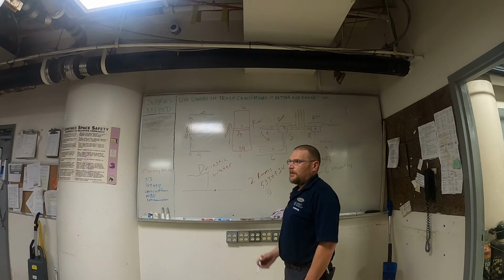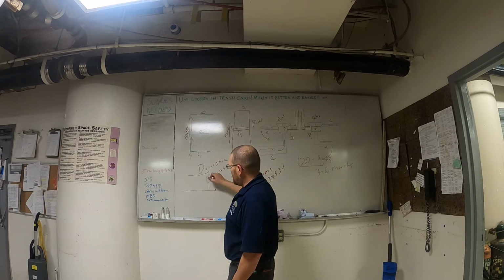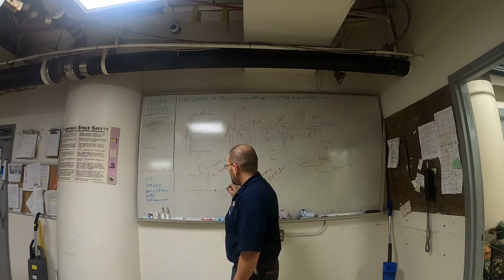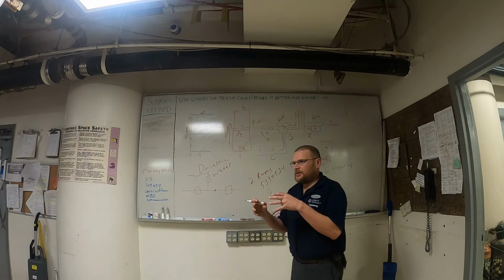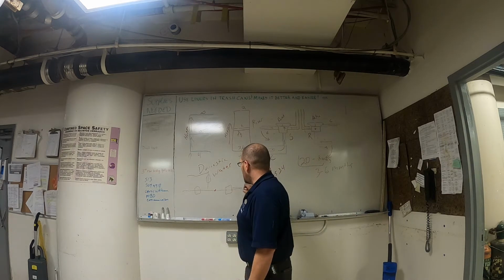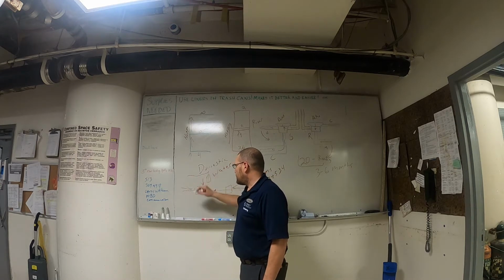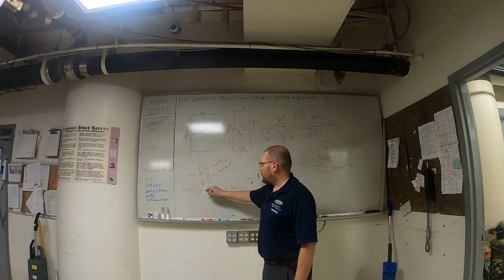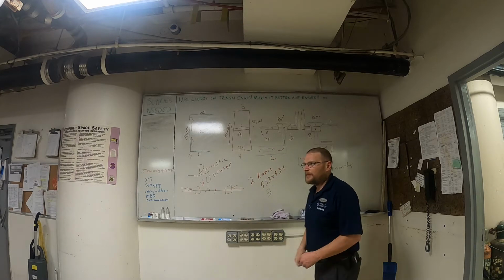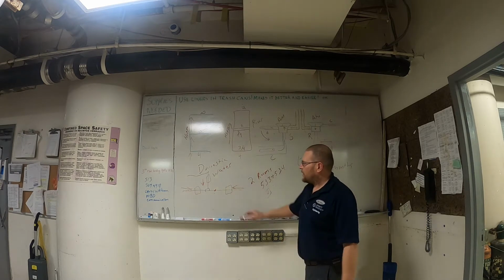Now, how am I going to cut the water off? Above and below, and before and after. So you're going to find the valve here, find the valve here, find the valve here. That way you've isolated that leak into that one little section and you stop water from flowing in, flowing back in, or flowing down. So there'll be no water on this. You cut here, put a T in here, put your piece of PEX in, you're good to go. Then go back and open your 3 valves again.